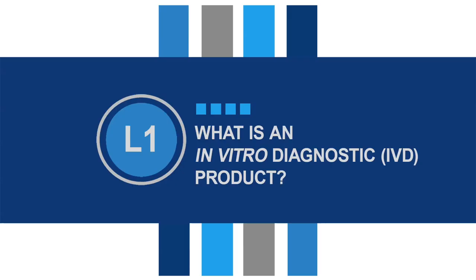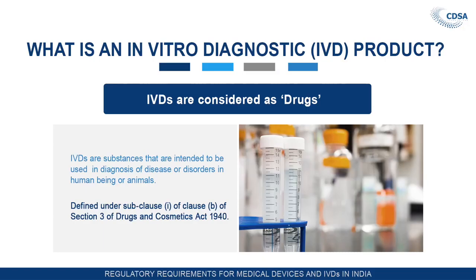Now let's look at in vitro diagnostics. The general definition of medical devices covers in vitro diagnostics as well. However, as per the Drugs and Cosmetics Act, in vitro diagnostics are considered drugs — substances intended to be used in the diagnosis of disease or disorder in human beings or animals. In vitro diagnostic kits are defined as drugs under Section 3(b)(1) of the drug definition.